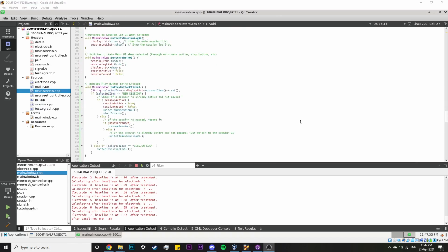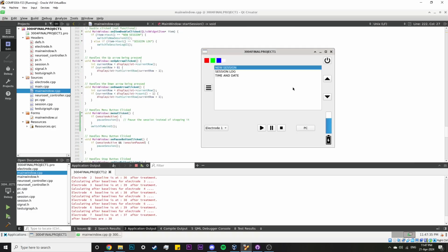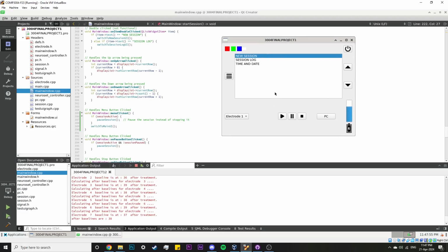For battery depletion, as we can see, the session has completed successfully, and after each session, the battery depletes a certain percentage based on the number of sessions run, and once it reaches a total of 3 sessions, it would deplete to the bottom. This is pretty much divided by 3, as stated in the spec, for it to deplete after 2 to 3 sessions.